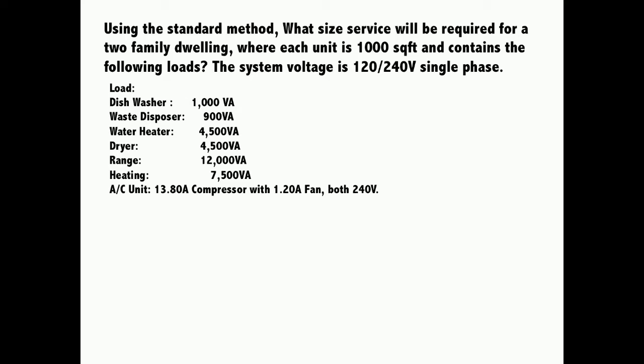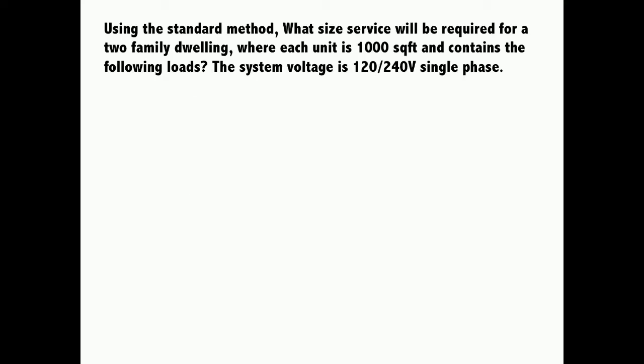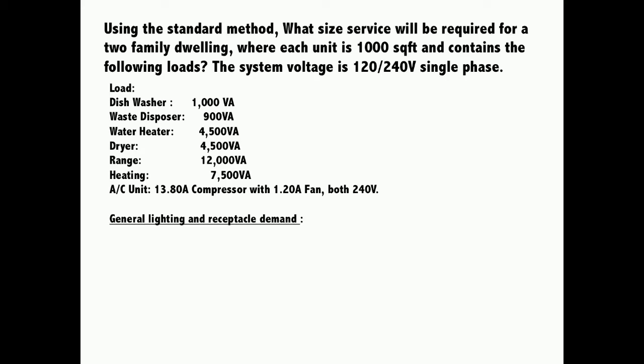We're going to apply demand factors for each load. The first thing we're going to take into account is the general lighting and receptacle load. For general lighting and receptacle, we should take into consideration the occupancy, and the occupancy demand is 3 VA per square feet. For this two-family dwelling we have two floors, so we would have twice the amount applied on each floor. For one floor it is 1,000 square feet, so applying 3 VA per square feet results in 3,000 VA per demand for one floor.